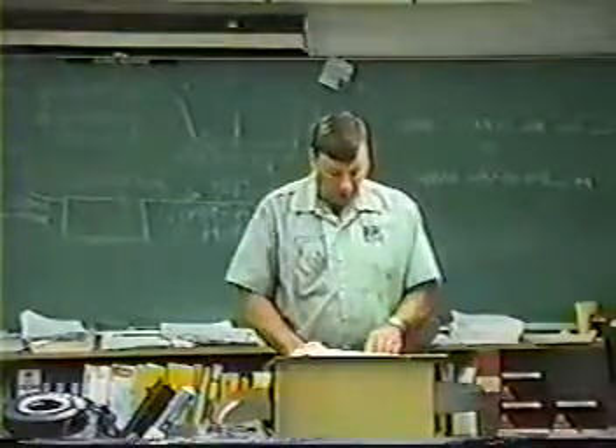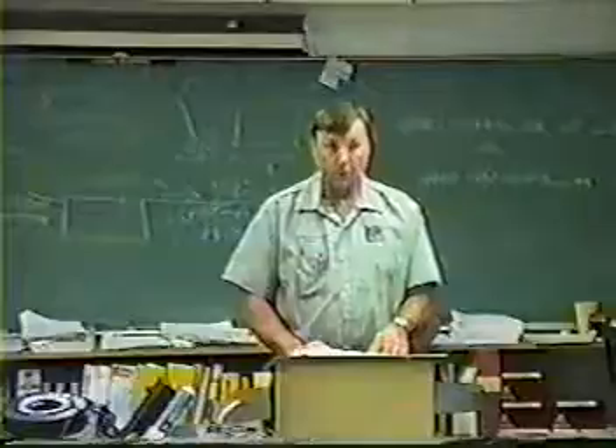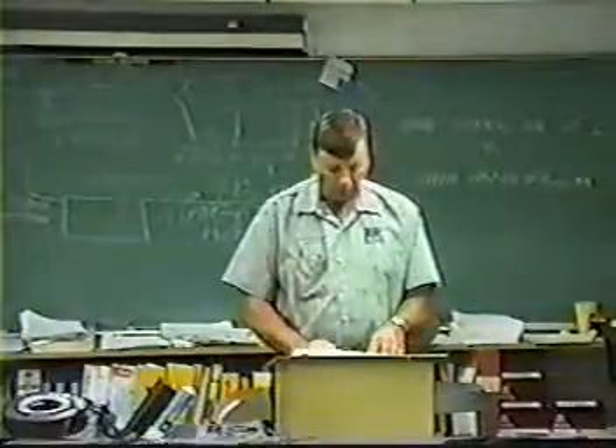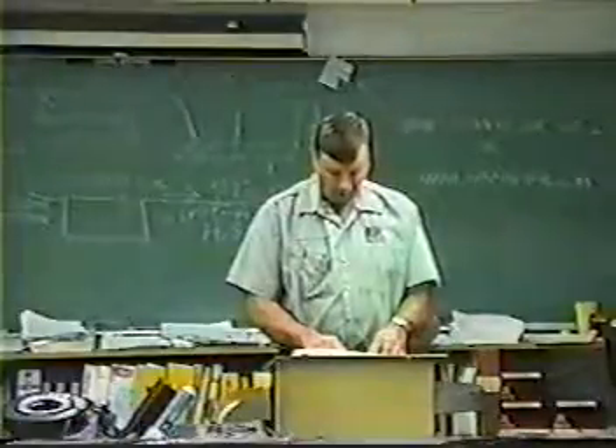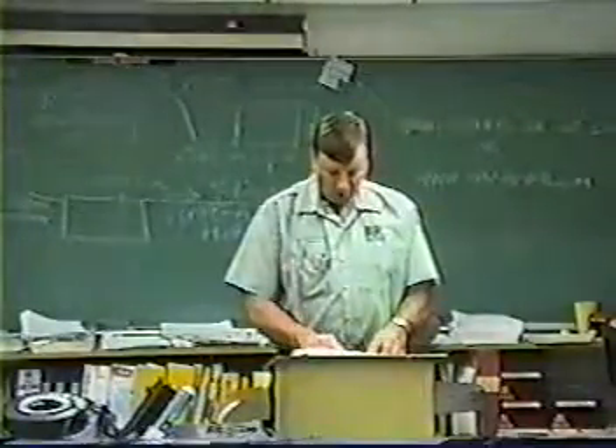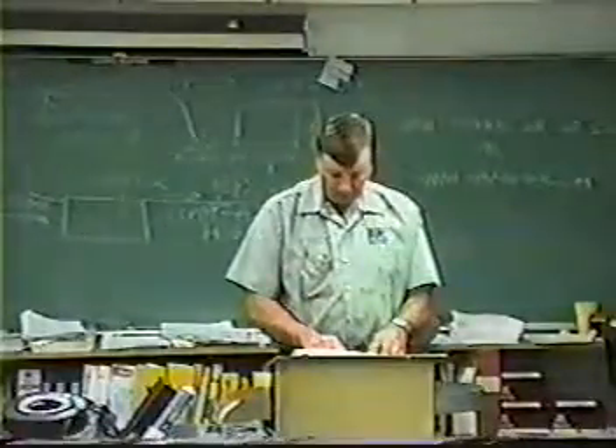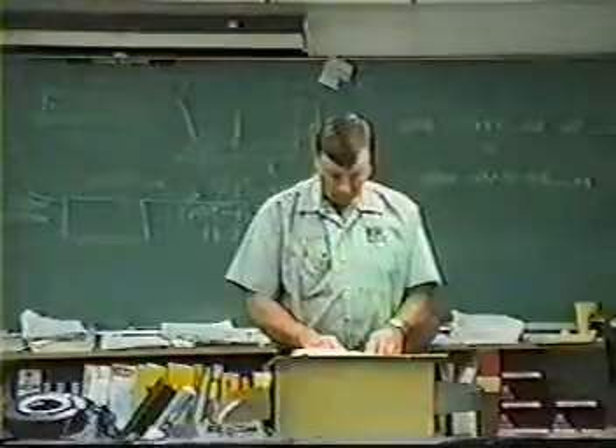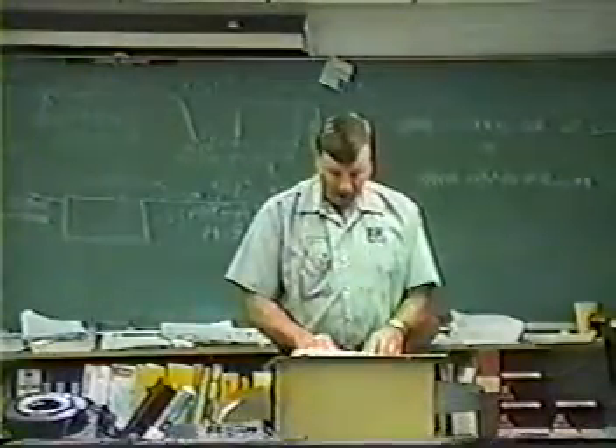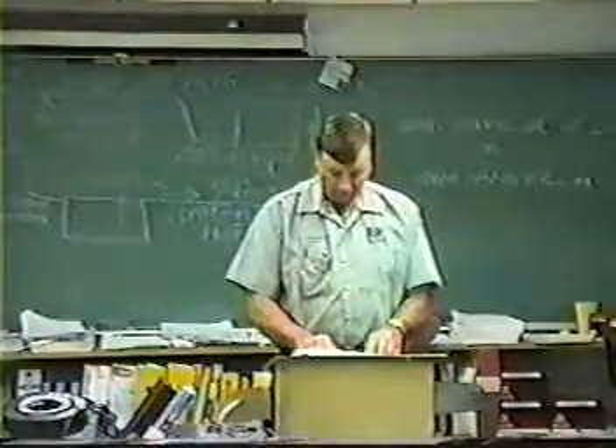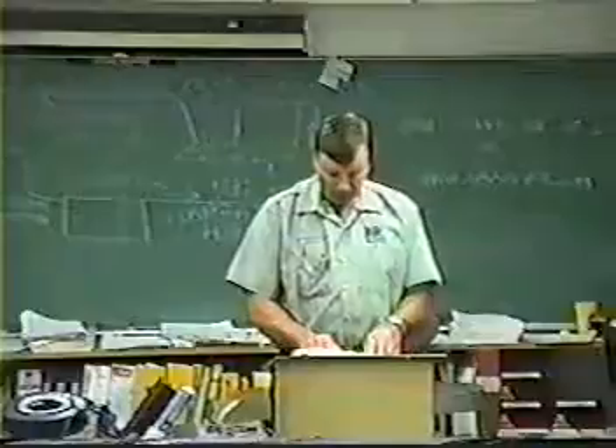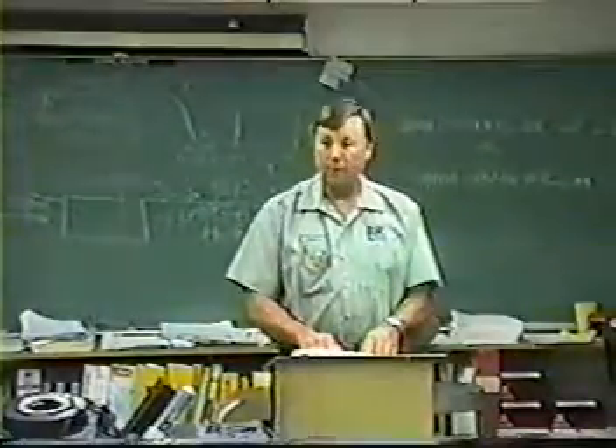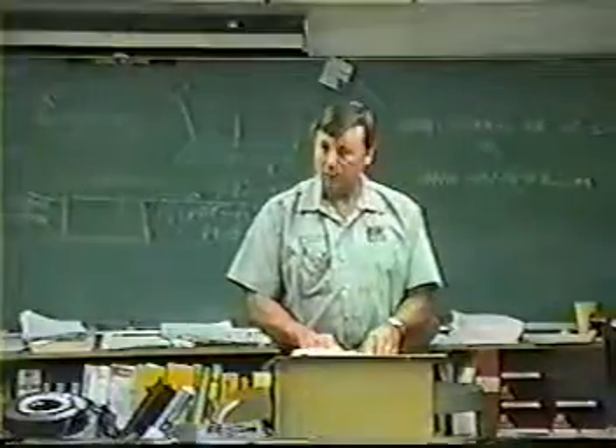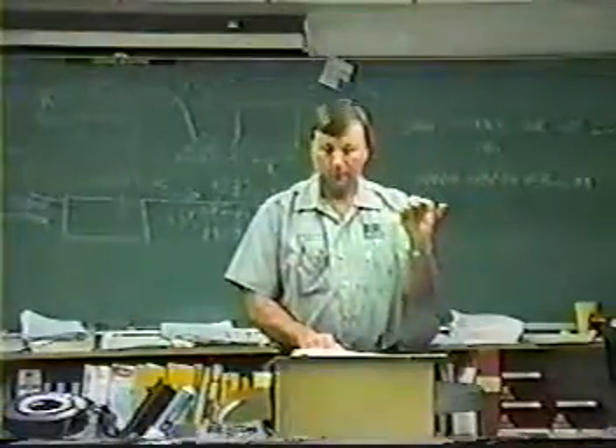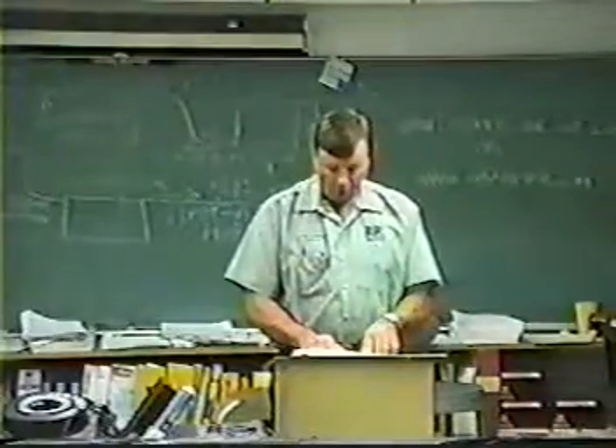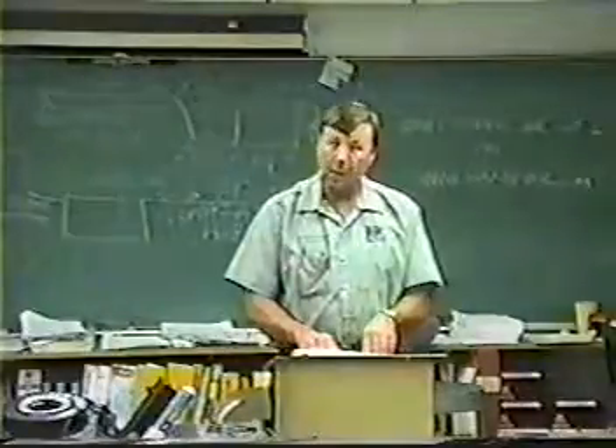If you look at those temperatures right there, you don't see 32 degrees, but you'll see it on your PT chart, but you see 40 degrees and 30 degrees on temperature Fahrenheit. Come across to the Freon 12, at 30 degrees is 28.4, at 40 degrees is 37.0 PSIG. R22, 68.5 at 40 degrees. So that means if you got a system that you're running a 54.9 suction pressure, that means you run about a 30 degree coil. That means you got a freezing coil. That's on R22. That's what that means. 32 degrees is the magic number. So if you run a 54 then that means you got a 30 degree coil. That means you got some cold air coming off that coil, but it ain't going to be for long because it's going to freeze.